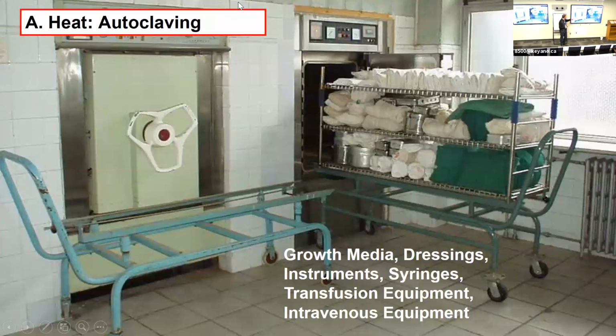So I think I have a picture here. You can see here's an autoclave in a hospital setting, and it's kind of hard to tell what all those things are, but you can see we're looking at bed sheets, so a lot of instruments like scissors, scalpels, those kind of things can be autoclaved. A lot of those tools that you may have had put in your mouth at the dentist, right? The dentist probably has an autoclave. Sometimes they do 2 methods of sterilization at the dental office, but autoclave is what they do. They stick them all in there.